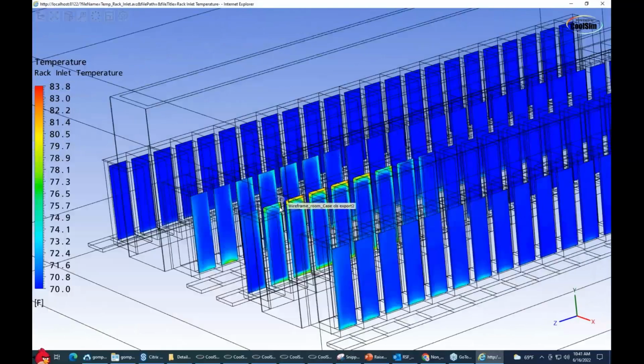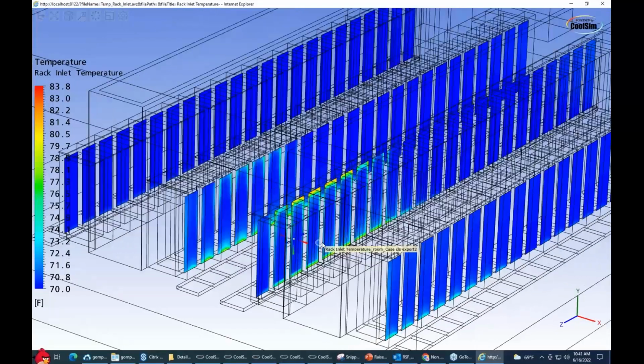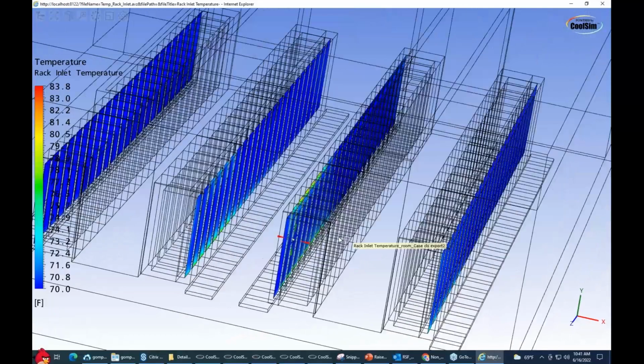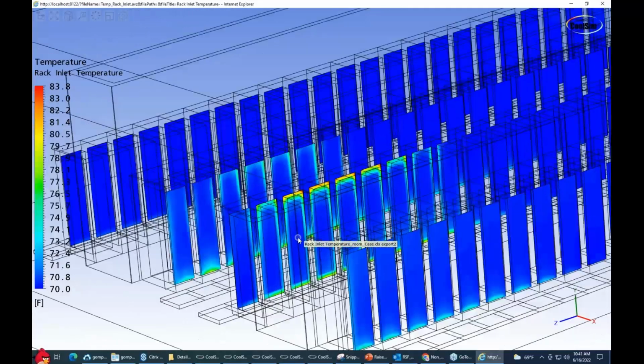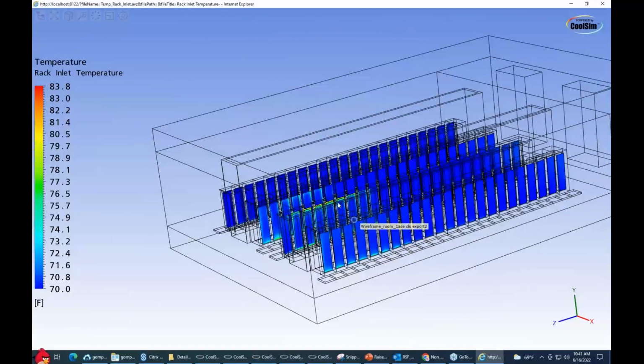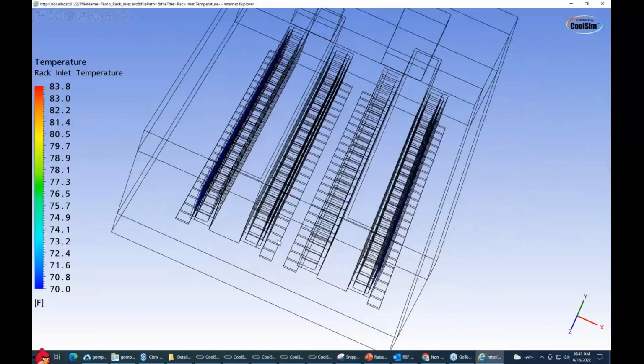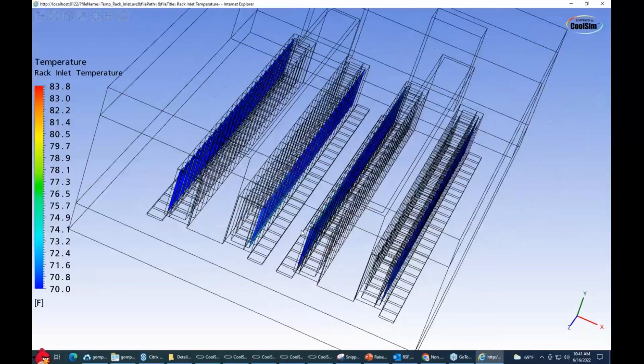As I mentioned, these are leaking a little bit due to the velocity and the lack of air by the time you get there. But because you have tiles, you can begin to bias this design to make up for that. Basically, steal from Peter to give to Paul is a saying that we use a lot, right? And I've only got one tile in front of each one of those.